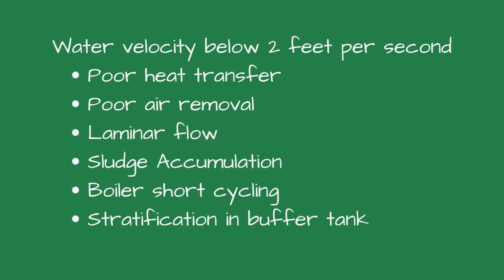What happens if the water velocity is below 2 feet per second? You get poor heat transfer. Water moves too slowly to effectively transfer heat from the boiler to the terminal units. Zones furthest from the boiler may be underheated, leading to customer complaints about cold areas. Heat exchangers may not perform efficiently, resulting in short cycling.